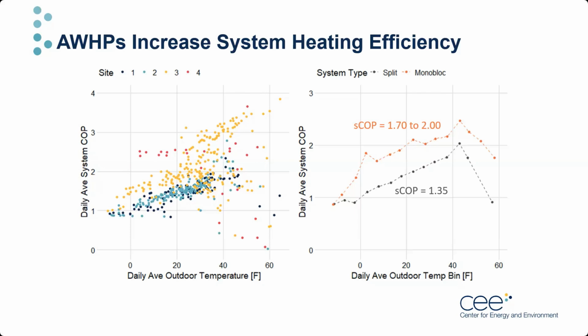Below zero, all system COPs fell toward that of the aux heat sources, as the heat pumps were used less and less. The monoblock systems were able to maintain COPs above 1 to slightly colder temperatures than the third-party split, which had a higher ODU lockout temperature of -4 degrees Fahrenheit. The seasonal COP for the split system was 1.35 and was between 1.7 and 2 for the monoblock. Next slide.